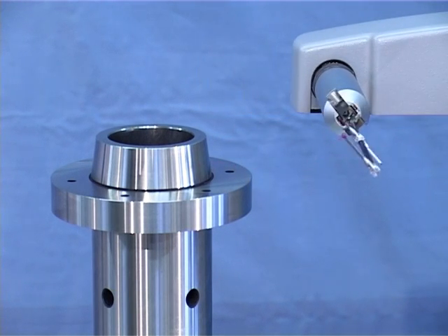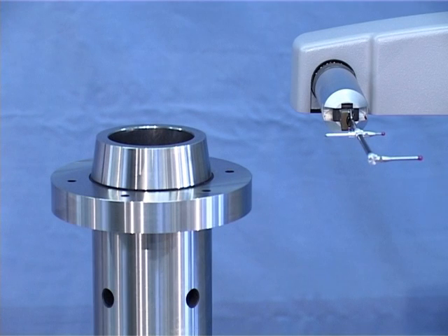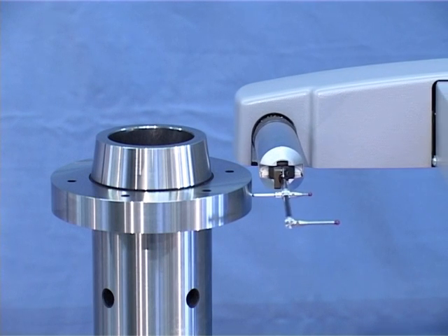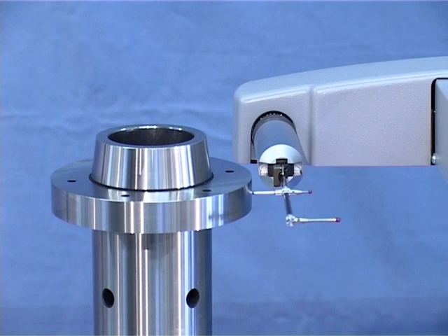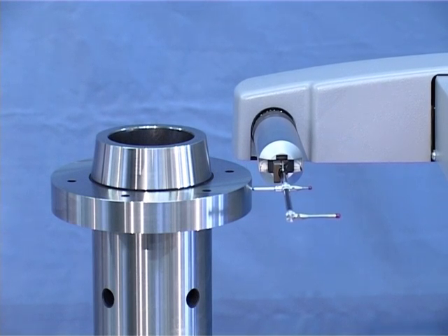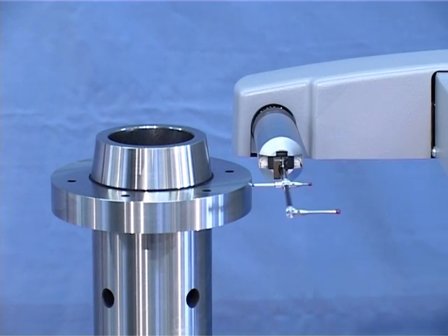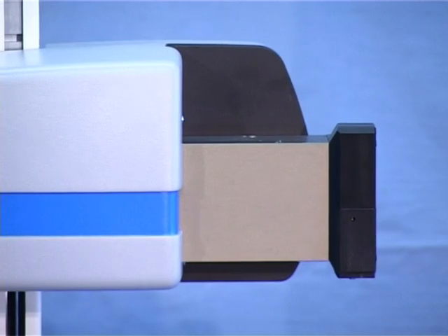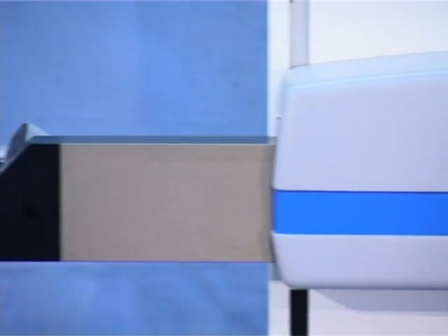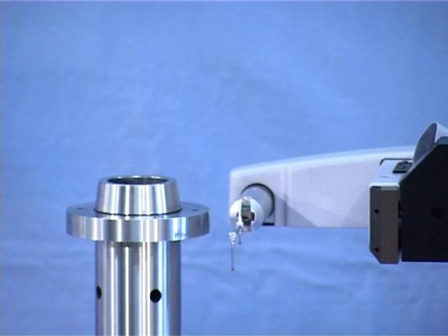A specially developed scanning system allows combined automatic measurement of form and roughness characteristics in one measuring run. The measuring instruments of the Hommel RoundScan series are therefore an investment in precision and economy. In addition to the added benefits of the peak to valley height measurement, nine very fast CNC controlled axes ensure short measurement times.